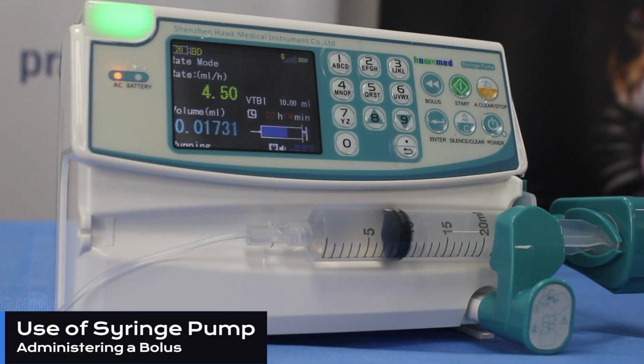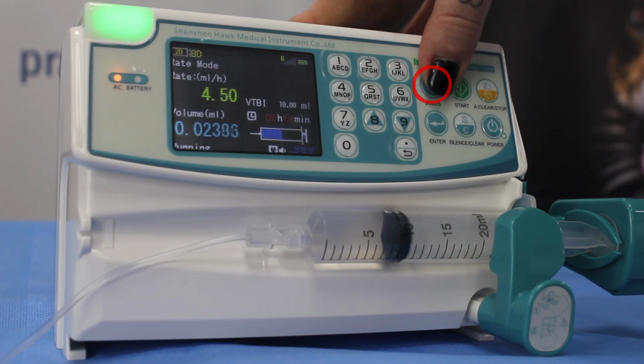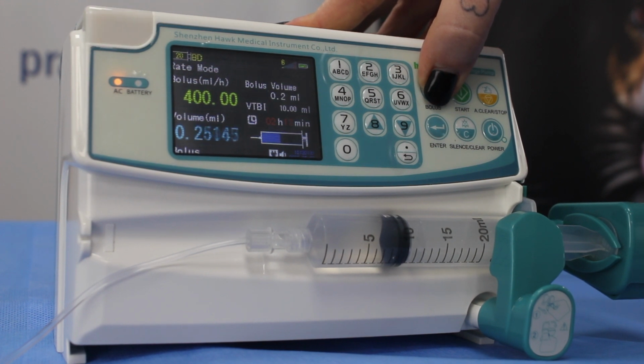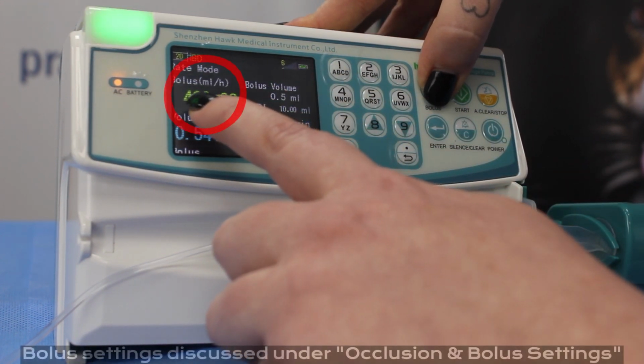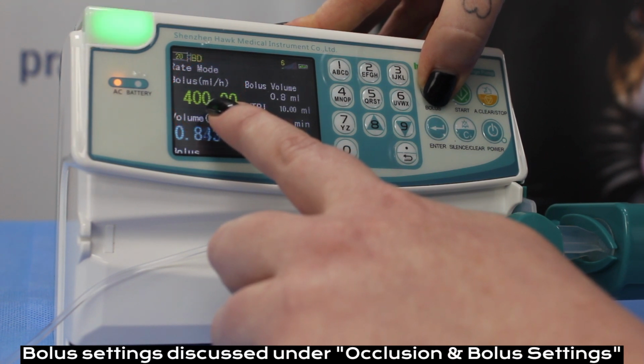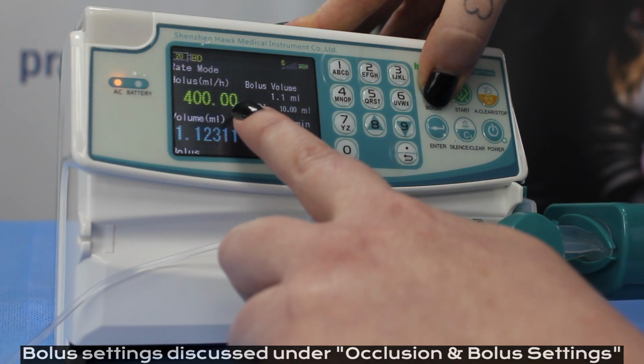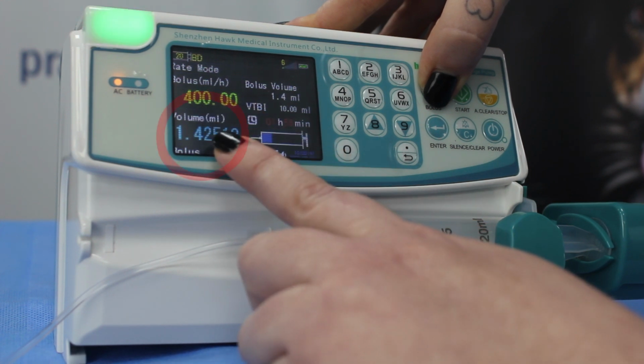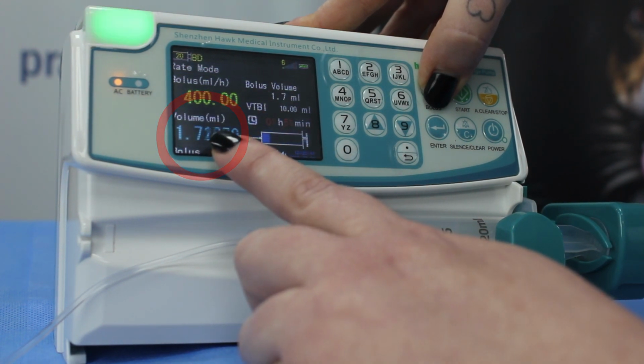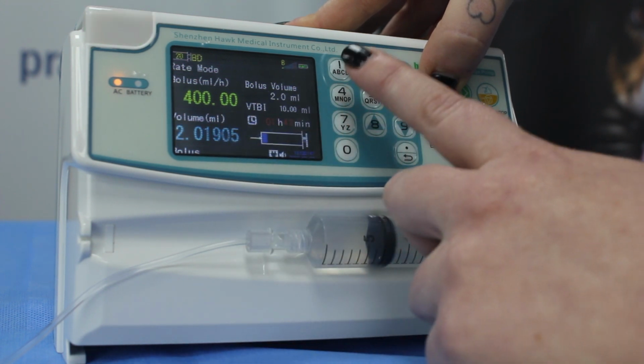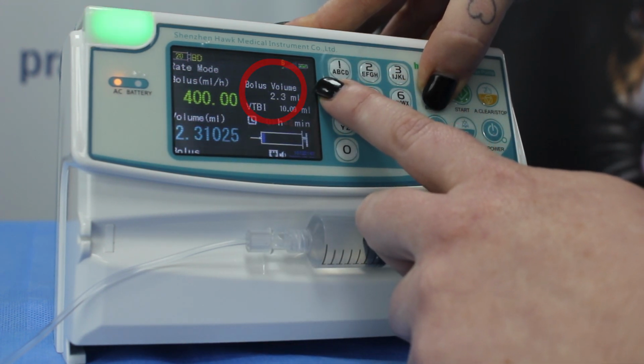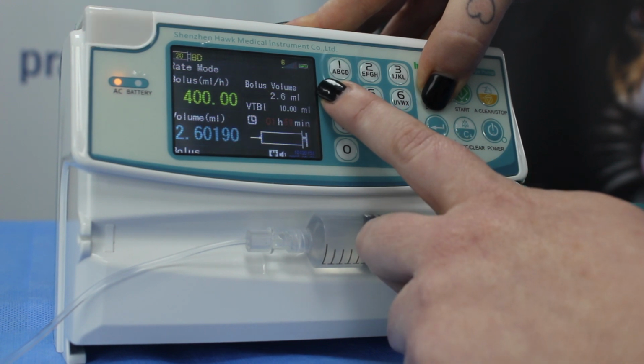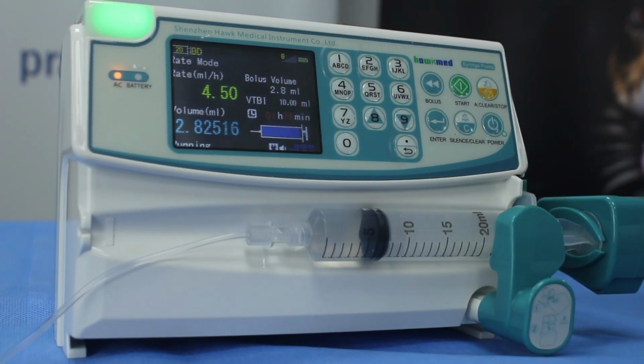To administer a bolus for your patient, you can do so by holding down the bolus button. We can see this is now bolusing at a previously set rate of 400 mils per hour, which we'll discuss shortly how to set this for each syringe size. We can see our volume infusing is increasing quite rapidly as the bolus rate, and our bolus volume is being recorded at the top here. When we stop pressing the bolus button, the bolus will stop and return to our previously set rate of mils per hour, which is 4.5.